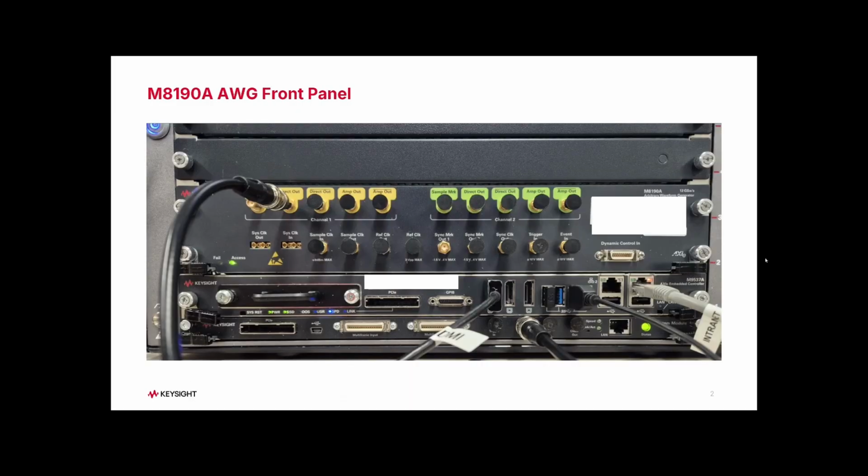Now let's just quickly look at the front panel just so you have a better idea of the ports that are available. So in my previous photo, you would have seen the display port that's connected to the monitor, so that you can see the whole front panel of the AWG. I also have this connected via LAN, so I could remote into it. So these are the two direct out ports. I have here only channel 1 with the cable. I have this without the cables, just so you could see the other ports that are available on the M8190A. Alright, so now that we're clear with the physical connections, let's have a look at the front panel.